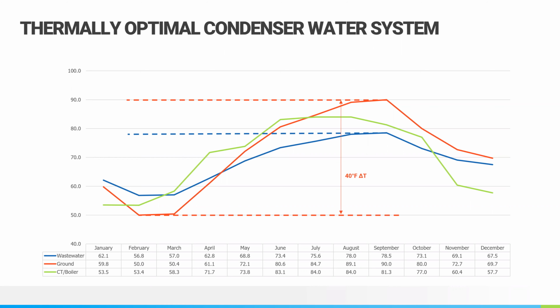So that was one thing that really came out of the system there on site too, versus the ground, where they had a 40-degree delta between its peak and its low. There's a vast range of temperatures that system would be seeing. And then for the cooling tower boiler, it was a little bit less of a delta, and for the wastewater heat recovery system, it was even less.